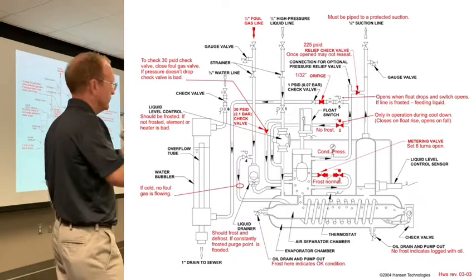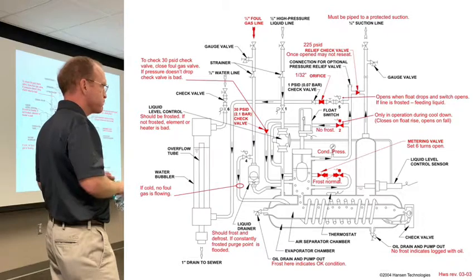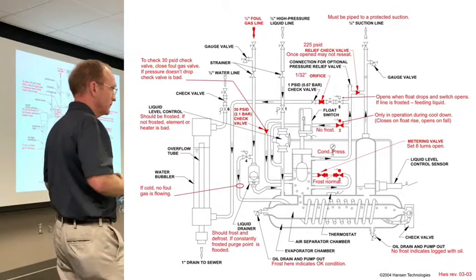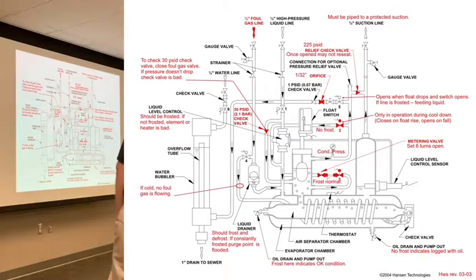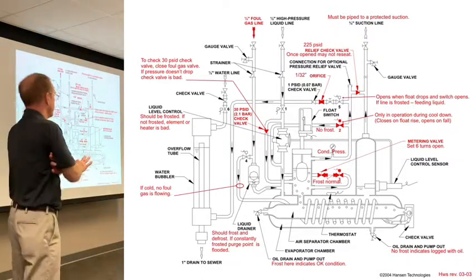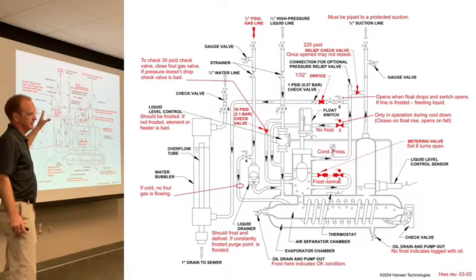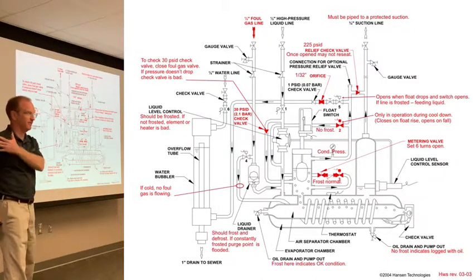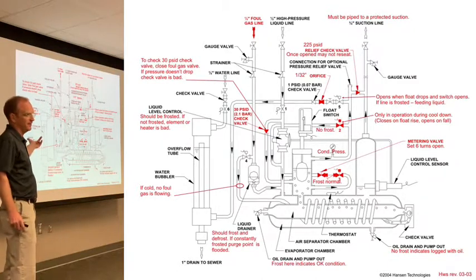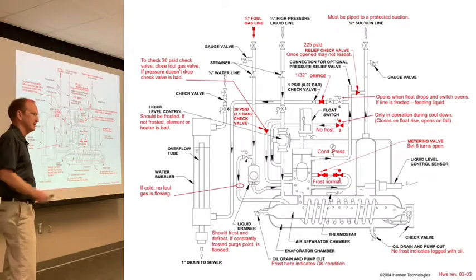Yeah, it's really what it's there for. Right. I'm wondering if that may have happened to our auto purger in the past, so I'm wondering if we don't have that problem right now. And to me, if your purger's a block of ice, I can tell you, pump it down, let all the ice melt away, start it up again. Now you can see very clear, distinct lines. What happened? Yeah, very distinct lines.